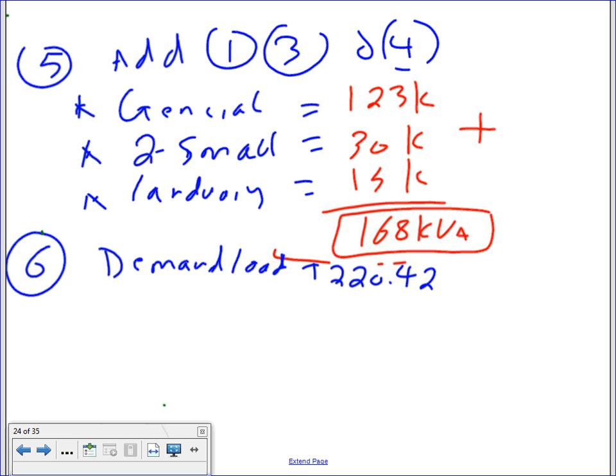So, because of all of this, you can derate, cut it down a little bit, reduce it. Where would these deratings come from, guys? These are statistical and experience. Statistically speaking, after you design it and they go measure the actual load, they came up with that there's no way you can get 168 kVA for lighting and receptacles for this part of our apartment. Okay, derating. How do we derate?